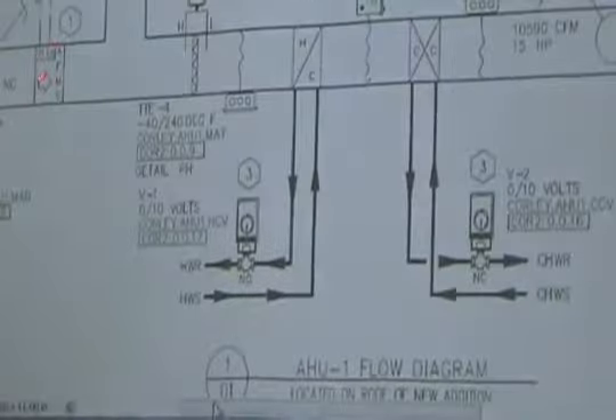When I start measuring here, and I've got, say, 10,000 CFM leaving the air handler, how much outside air do I need to give me 100% of fresh air in this one room?